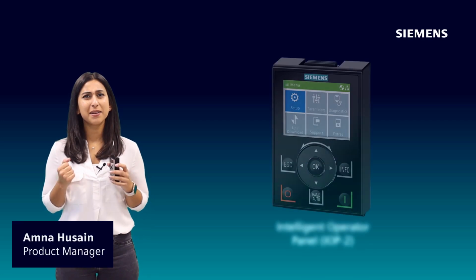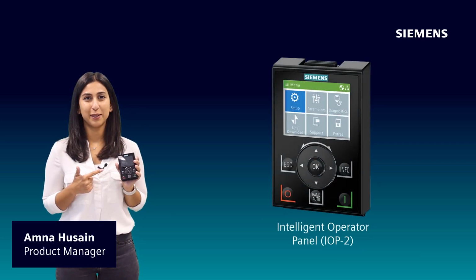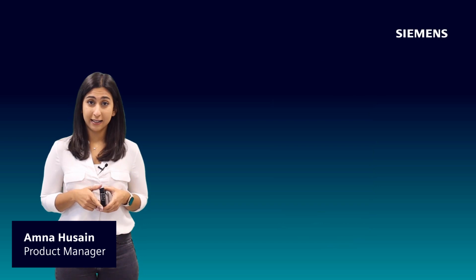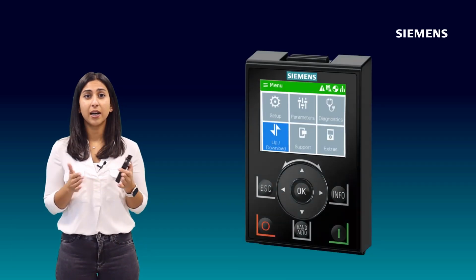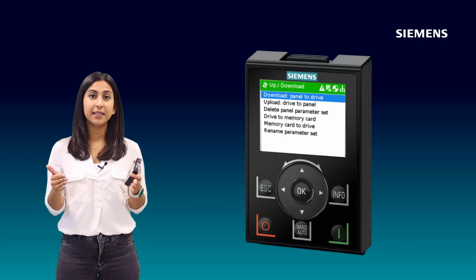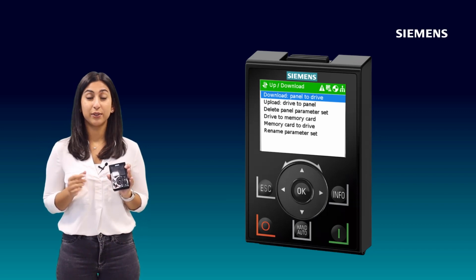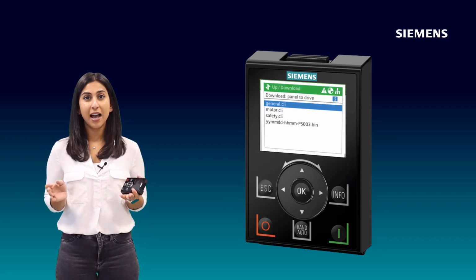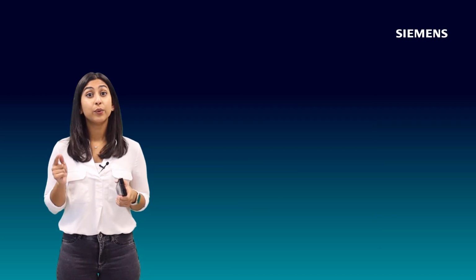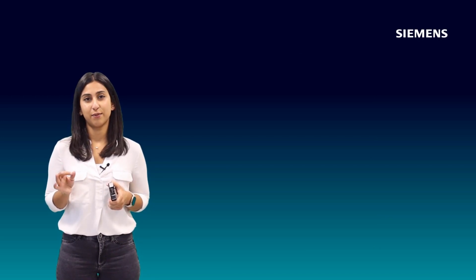Thanks, Axel. We have some exciting new functionalities in the IOP-2. Let me start with the CLI function. It allows you to download a custom parameter list directly to the drive using the IOP-2 download process. In addition, IOP-2 now keeps a record of all the parameters you have changed. You can export this list in the form of a CSV file.